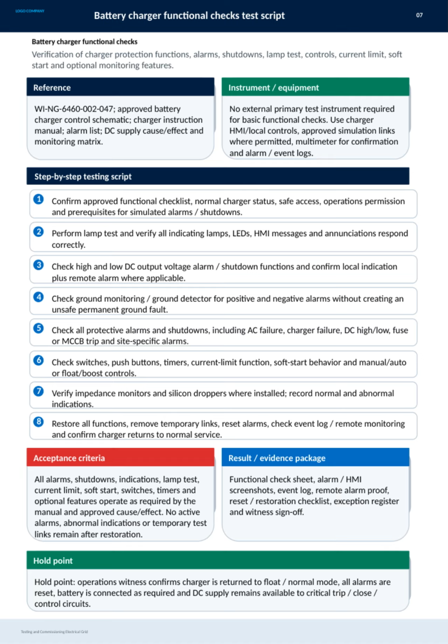We also test the ground monitoring system to detect any positive or negative alarms without causing unsafe conditions. Protective alarms, including AC failure, charger failure, and fuse or MCCB trips, are carefully examined to ensure they function properly. We proceed to test switches, push buttons, timers, as well as current limit and soft start functions, including manual and automatic control modes. Impedance monitors and silicon droppers are verified where installed, recording both normal and abnormal readings.